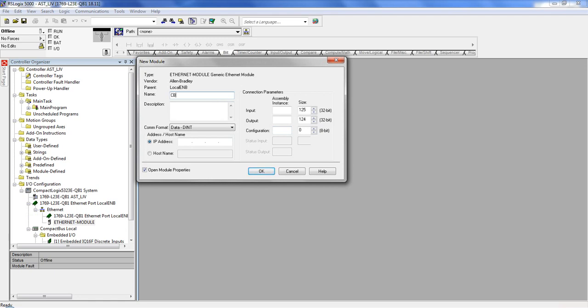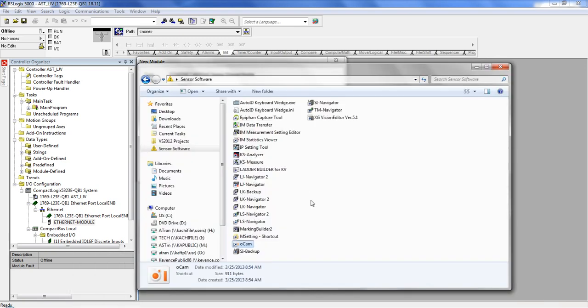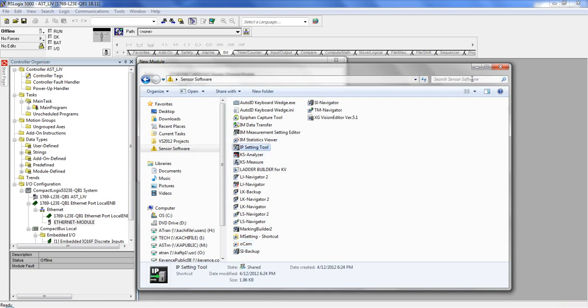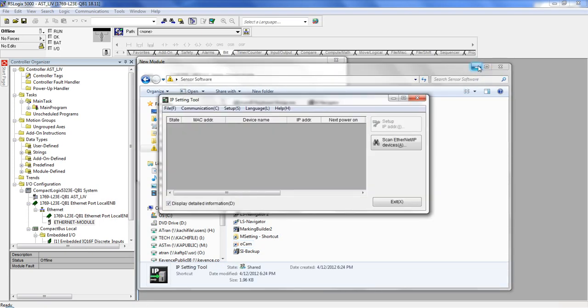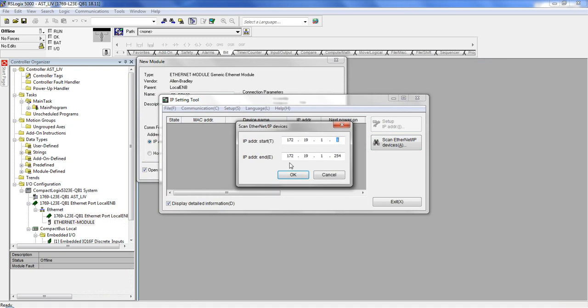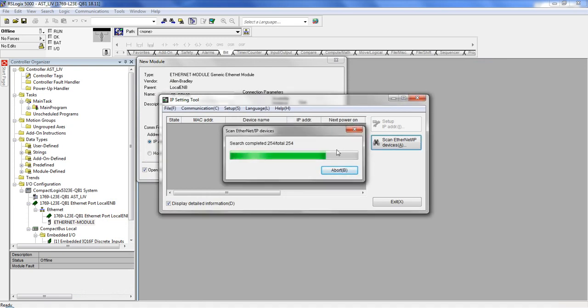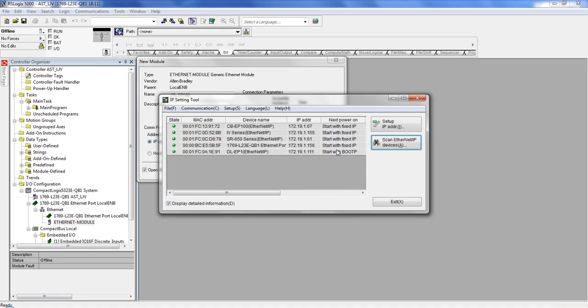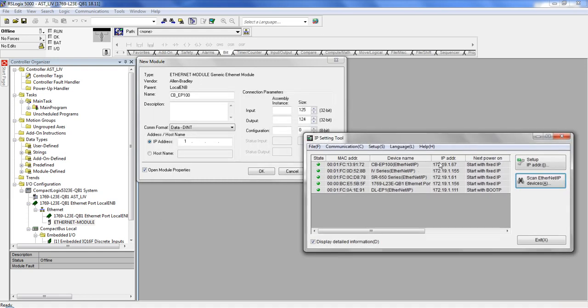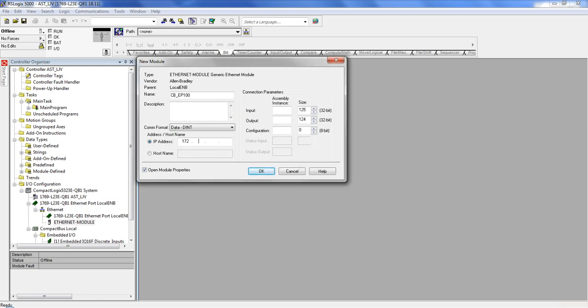We're going to name this CB_EP100. And for your purposes, I would recommend naming it exactly as I have shown here, as we're going to bring in some tags that are not generally provided. Here, I'm going to find the IP address. One thing to know is the IP setting tool. I know many of you have not really used this, but this can be a useful tool. It's used for setting the IP address of the units, as well as just viewing what all the IP addresses are. So here I found my CBEP100 module, and this is the IP address that is currently assigned to it. So that's what I want to use here. So I'll go ahead and put that in here.